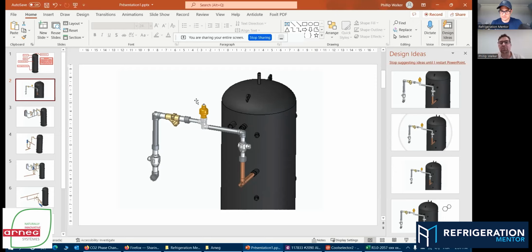And this improves the valve responsiveness, because don't forget, we're sizing systems based upon a worst case scenario. Well, as you walk into any mechanical room with a CO2 system in wintertime, you'll say, well, there's only 1 or 2 compressors running, right? It's just because of the way, at this moment, we're all sizing systems. So we've taken it a step further, added a second tank and a smaller valve that we can change over to in winter months.